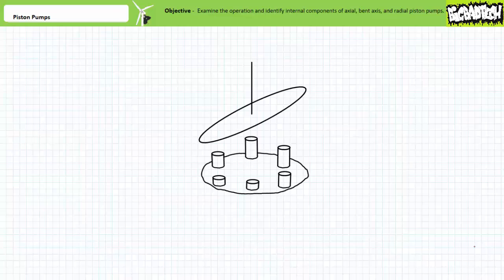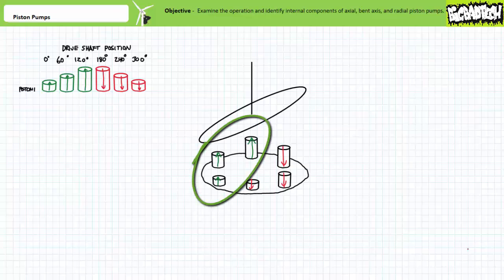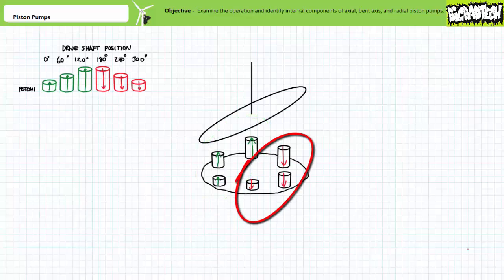The swash plate's only purpose is to create a volume differential at the opposite ends of the drive shaft's circular path. If you think about this from the perspective of a single piston traveling the full 360-degree circle, an individual piston is in effect acting just like a manual piston pump. The upstroke of the piston creates a region of increasing volume and executes the suction phase. The downstroke forms a region of decreasing volume and executes the compression and exhaust phase.